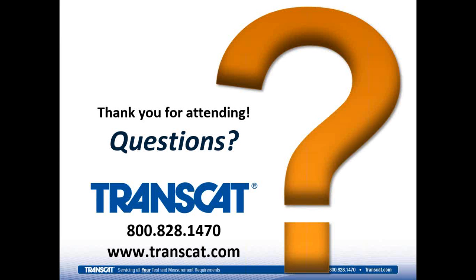Yeah, so conventional rounding rules apply because the circuitry in an instrument is going to do the same thing. It's going to take that next digit that can't be seen and either round down or round up based on that value. 4 and under would round down, 5 and up would round up. And since you can't see that last digit, there is that instrument repeatability or resolution uncertainty, and that usually is included as part of the measurement uncertainty for the calibration of the instrument. But you should also use that unseen digit as a factor in the TAR, converting the TAR to TUR, test accuracy ratio versus test uncertainty ratio.